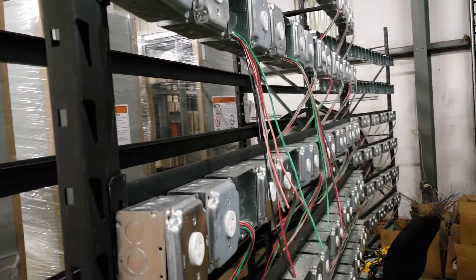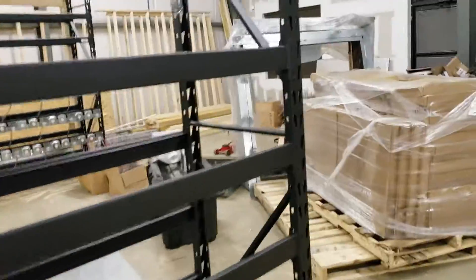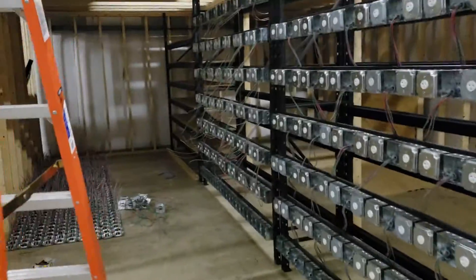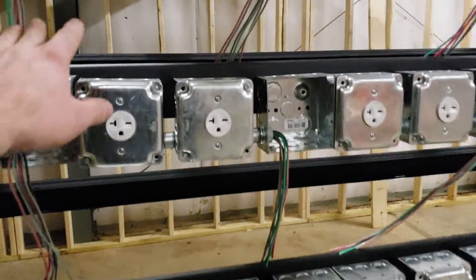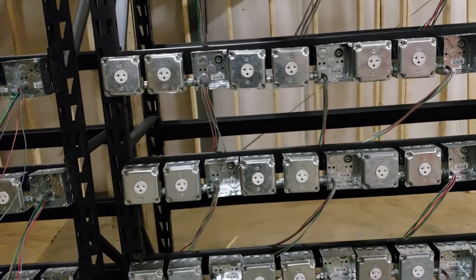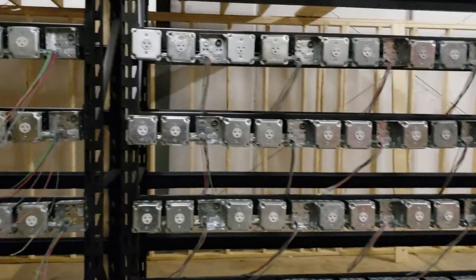That's what the fronts will look like. We are currently putting together tons of racks, getting everything ready. This is going to be the construction — this is how I've built quite a few for other people, but basically it's the same type of system. Everything is racked. The reason why we go this route: we go three per 20-amp circuit. This is the safest approach. I know I could use PDUs, but they cost 10 times more and they really don't give you a lot of value. I've had nothing but problems with PDUs in the past.